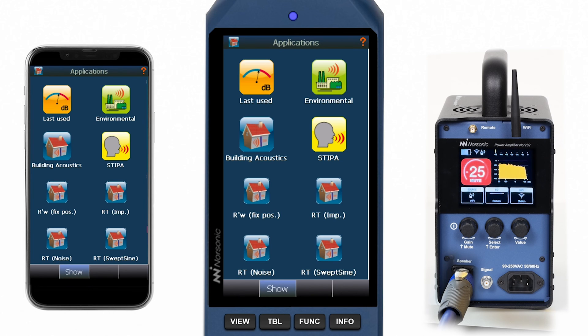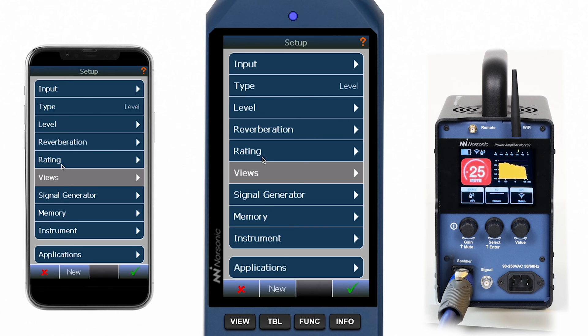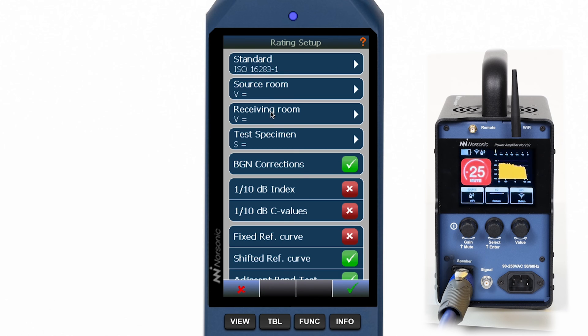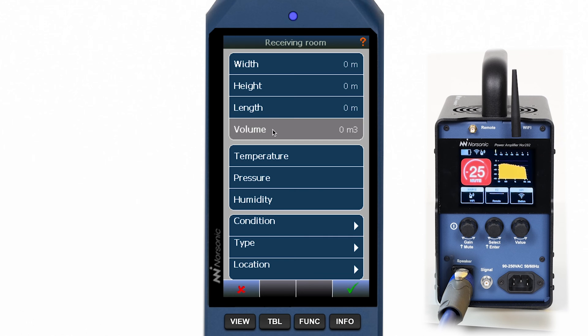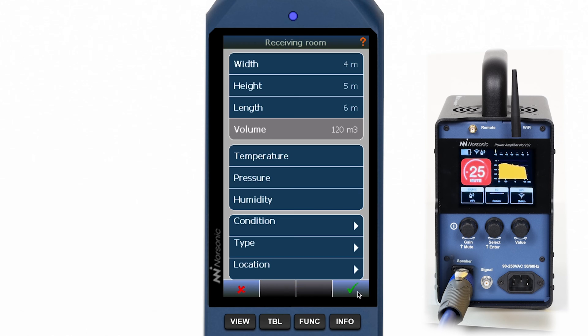Let's get started by loading the app — for example, the user setup called R-W with fixed microphone positions. Now everything is pre-selected according to this user setup. In the rating menu you can verify the selected standard, enter the receiving room volume and test specimen area. Changes in the rating menu can be made at any point in time.